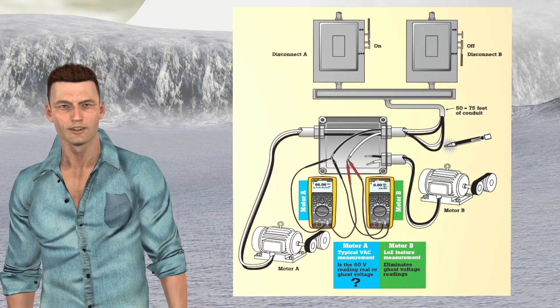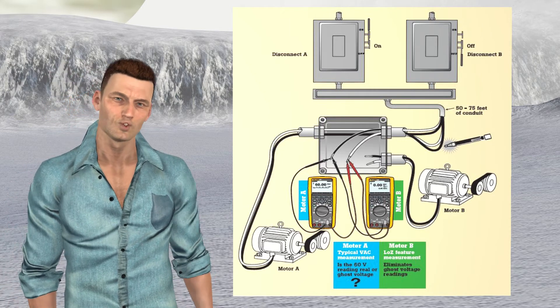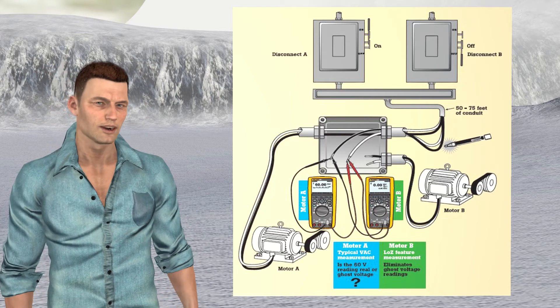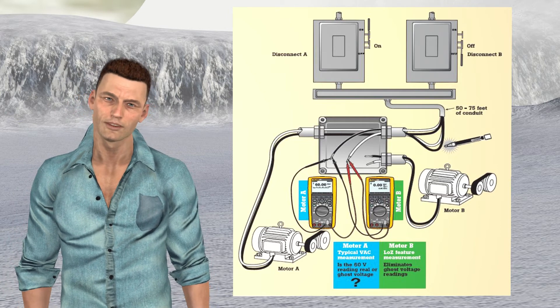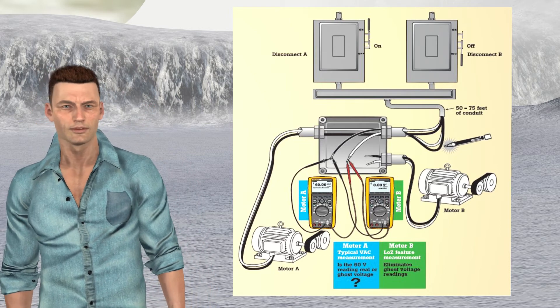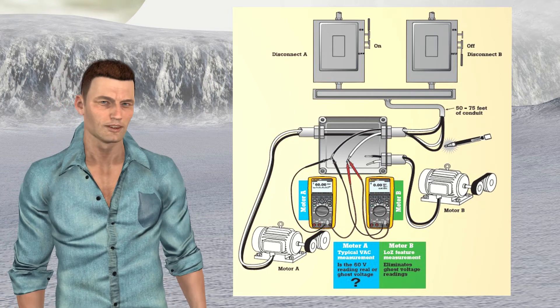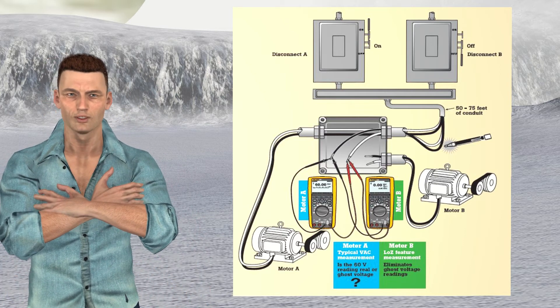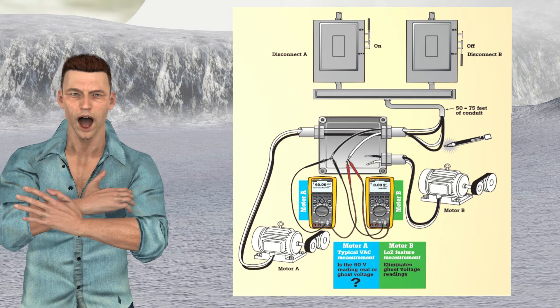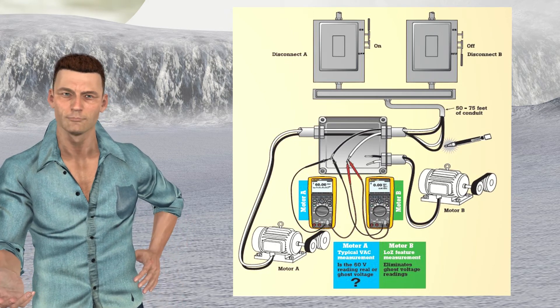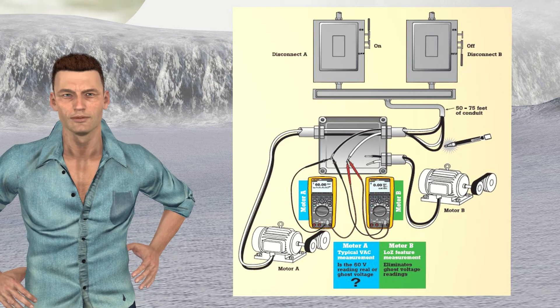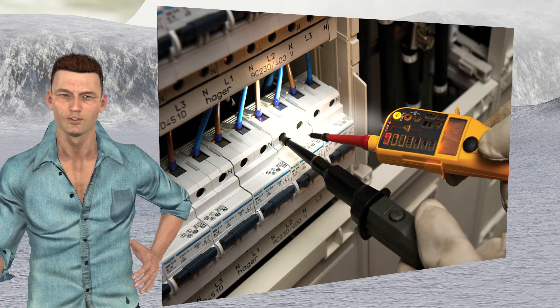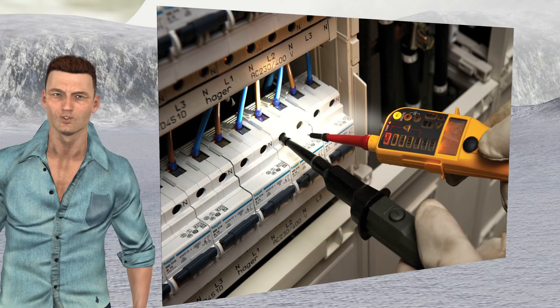How can you determine if a voltage is a real voltage or just a ghost voltage? The solution is simple: if we are facing a ghost voltage, when applying a small load the voltage will drop, while if it is a real voltage in an electrical distribution circuit, a small load will not influence the voltage. In the past, technicians used solenoid type voltage testers, which have a very low input impedance — typically less than 10 kilo ohms, but often as low as 1 kilo ohm — so this small load caused the ghost voltage to drop.